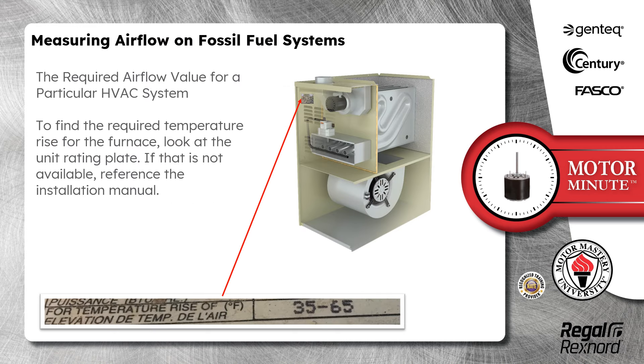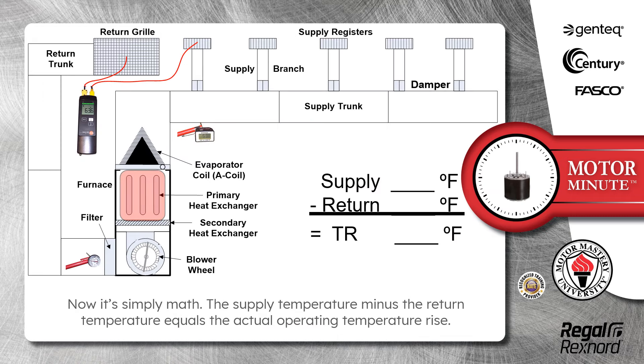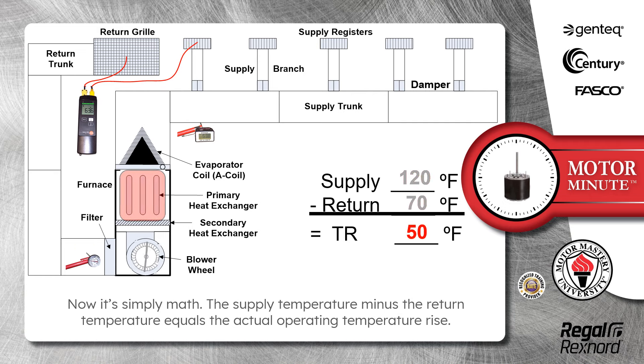To find the required temperature rise for the furnace, look at the unit rating plate. If that is not available, reference the installation manual. Now it's simply math: the supply temperature minus the return temperature equals the actual operating temperature rise.